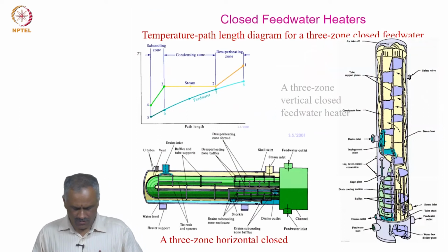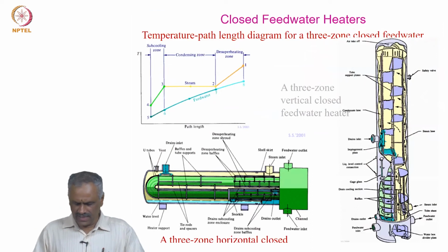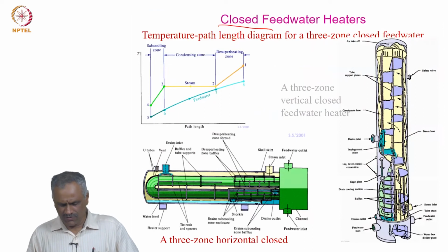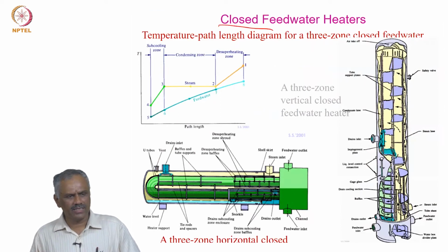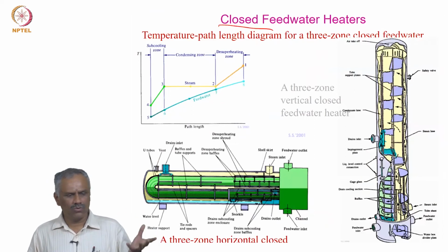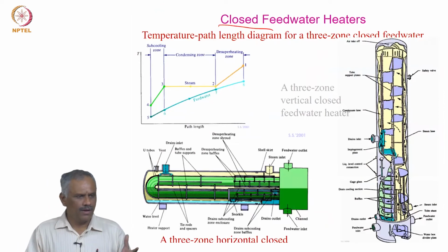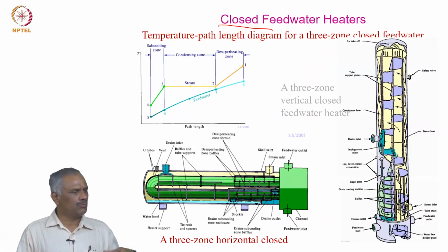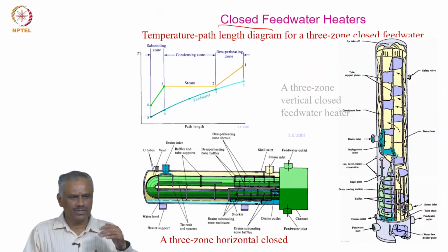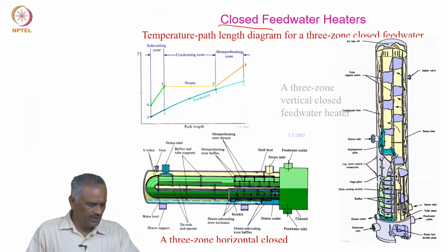In this cooling part, first we will discuss how closed feed water heaters look. It is a heat exchanger we discussed in the cycle analysis. There are closed feed water heaters and open feed water heaters. In any plant, most are closed feed water heaters, and there will be only one open feed water heater, which is the deaerator that we discussed.